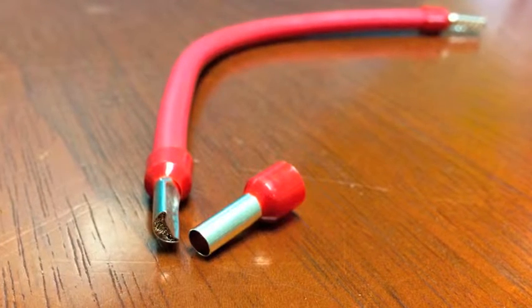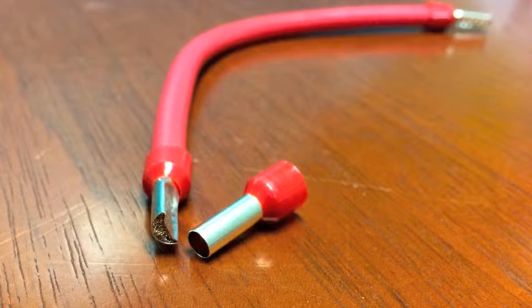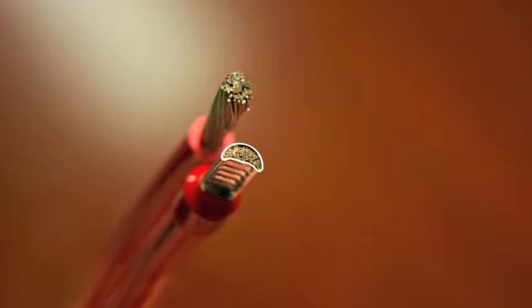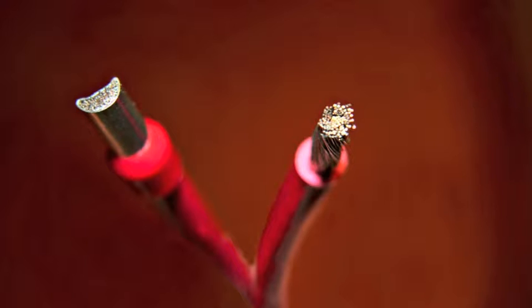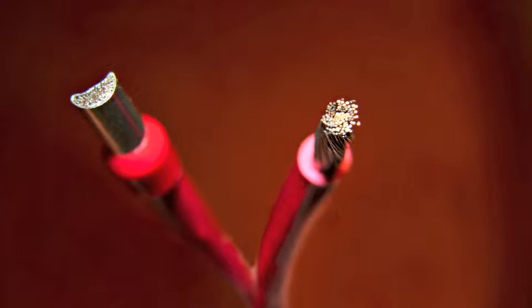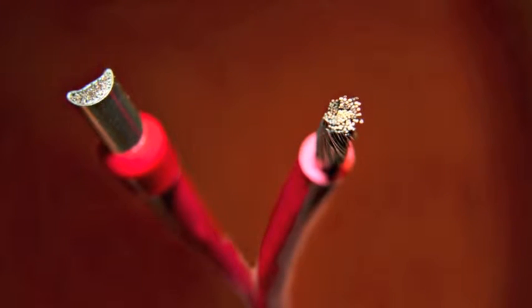However, these need to be examined on a case-by-case basis to determine feasibility. We need to look at the number of wires being crimped, the type of insulation used, and the length of the wire. In some cases, it is easier to use the machine to crimp a loose-piece ferrule than it is to try to insert multiple wires into the tape-mounted ferrule.